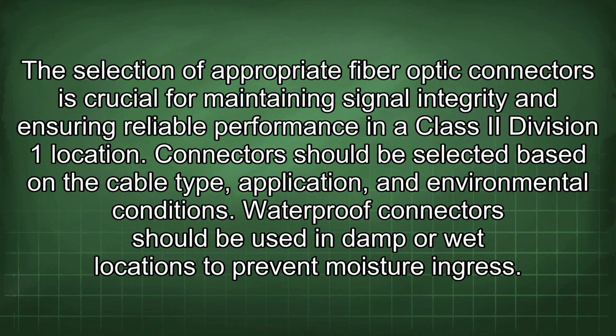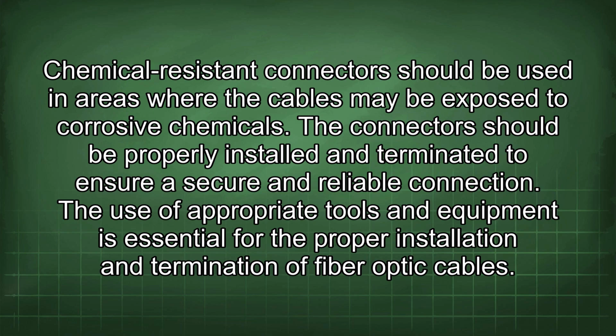The selection of appropriate fiber optic connectors is crucial for maintaining signal integrity and ensuring reliable performance in a Class II Division 1 location. Connectors should be selected based on the cable type, application, and environmental conditions. Waterproof connectors should be used in damp or wet locations to prevent moisture ingress. Chemical-resistant connectors should be used in areas where the cables may be exposed to corrosive chemicals. The connectors should be properly installed and terminated to ensure a secure and reliable connection.